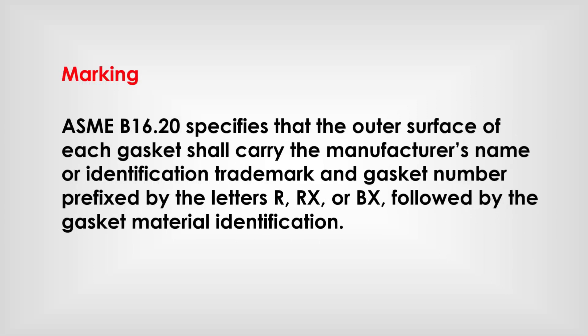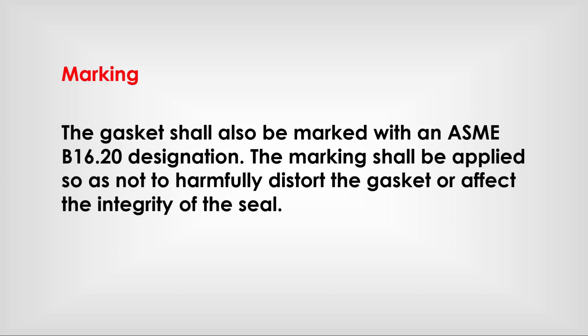Marking: ASME B16.20 specifies that the outer surface of each gasket shall carry the manufacturer's name or identification trademark and the gasket number prefixed by the letters R, RX, or BX, followed by the gasket metal identification. The gaskets shall also be marked with an ASME B16.20 designation. The marking shall be applied so as not to distort the gasket or affect the integrity of the seal.